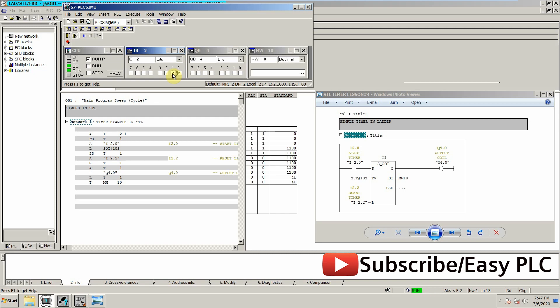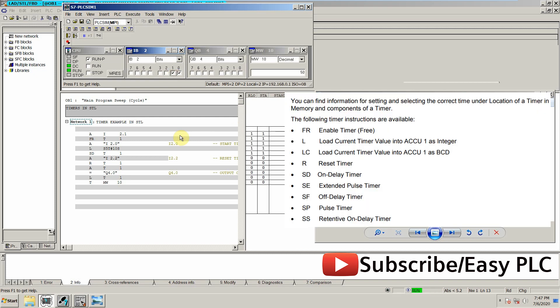So that's how we can write the STL code for the on-delay timer. And this is the list for the codes—we can write the code for the pulse timers and retentive timers, on-delay, off-delay timer using this code. We have to just replace here—instead of this SD on-delay time, we can use these codes to run off-delay.